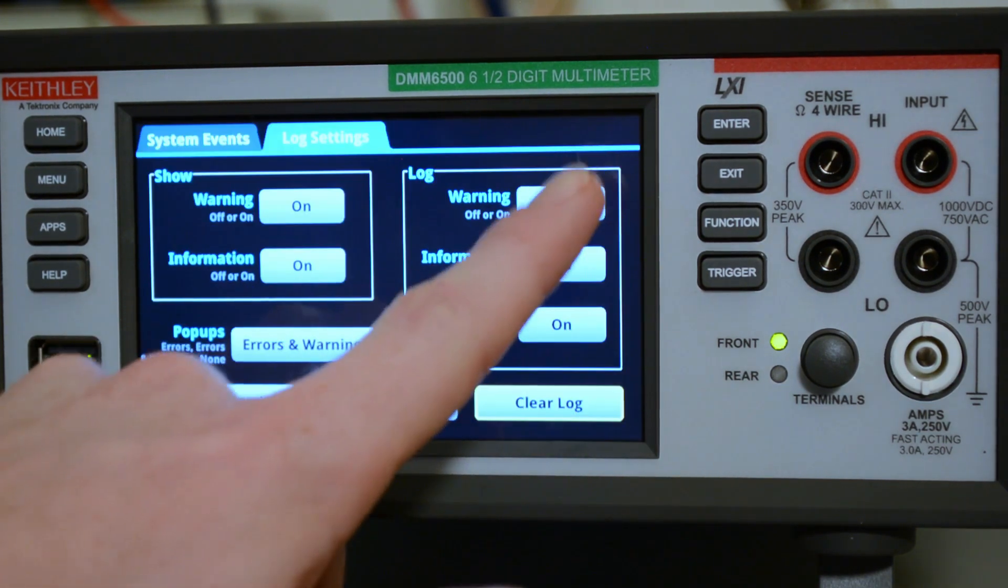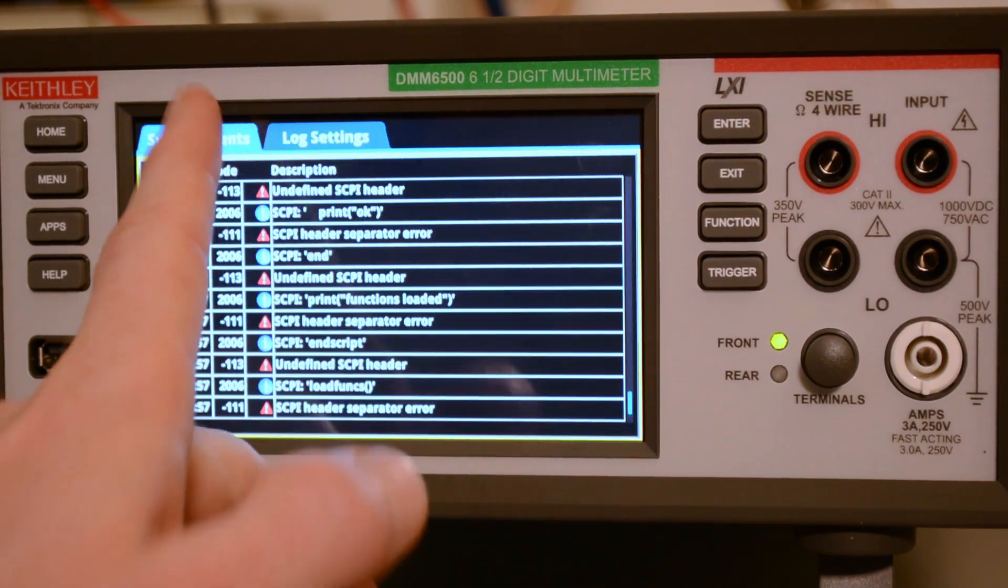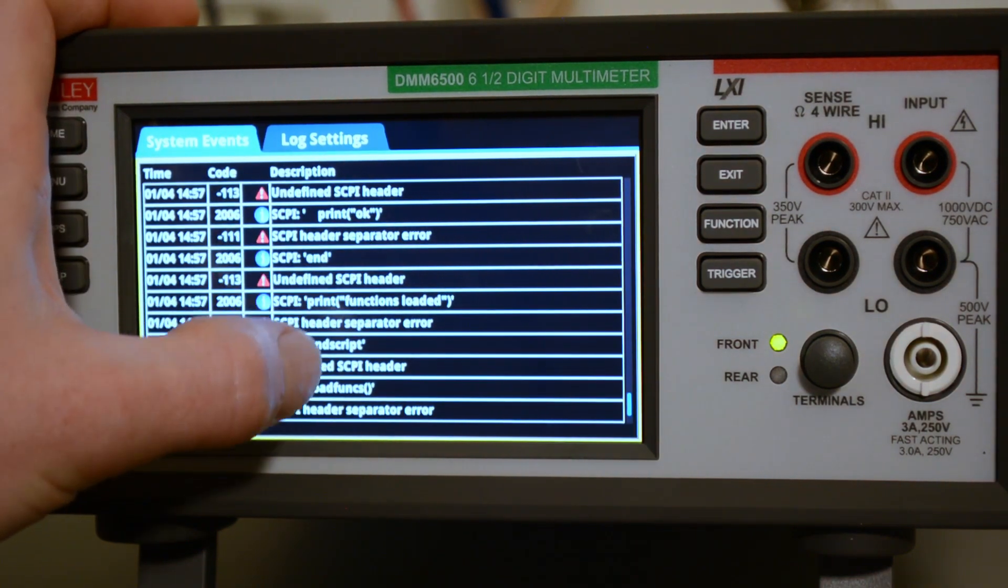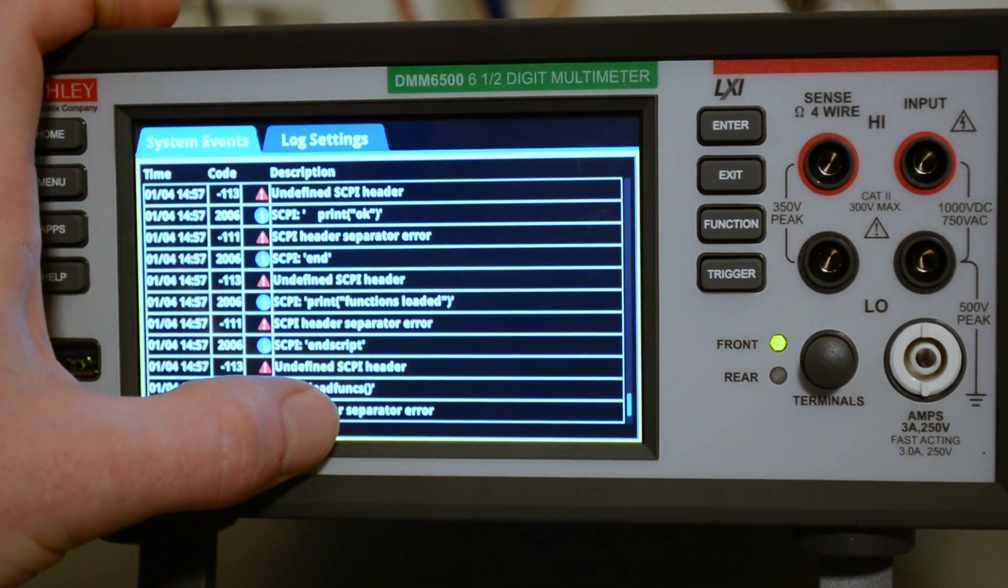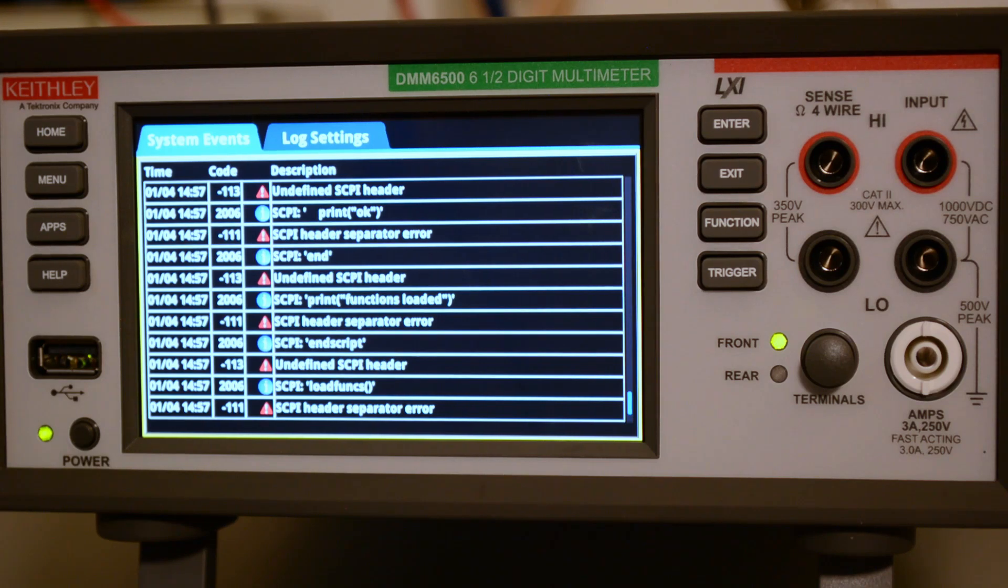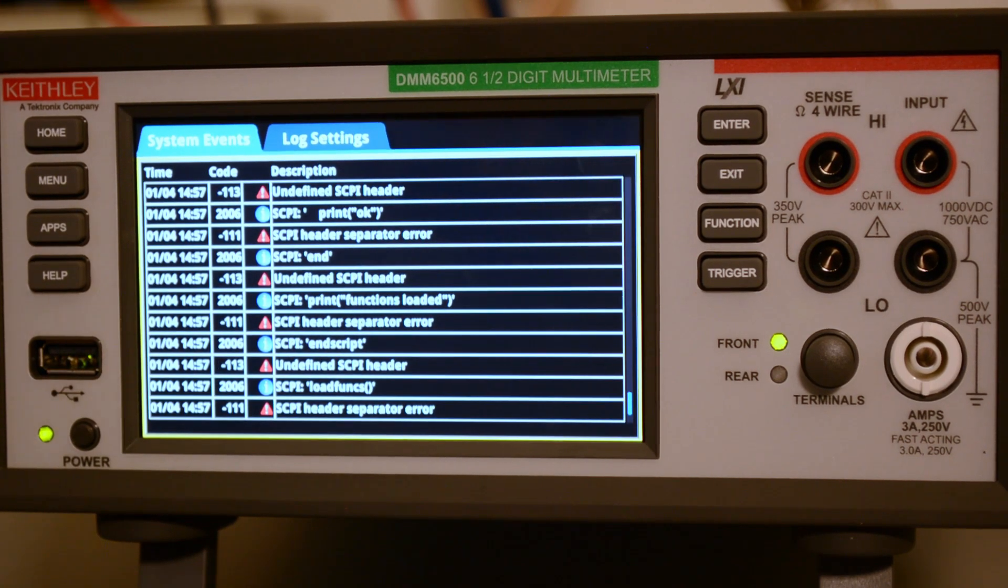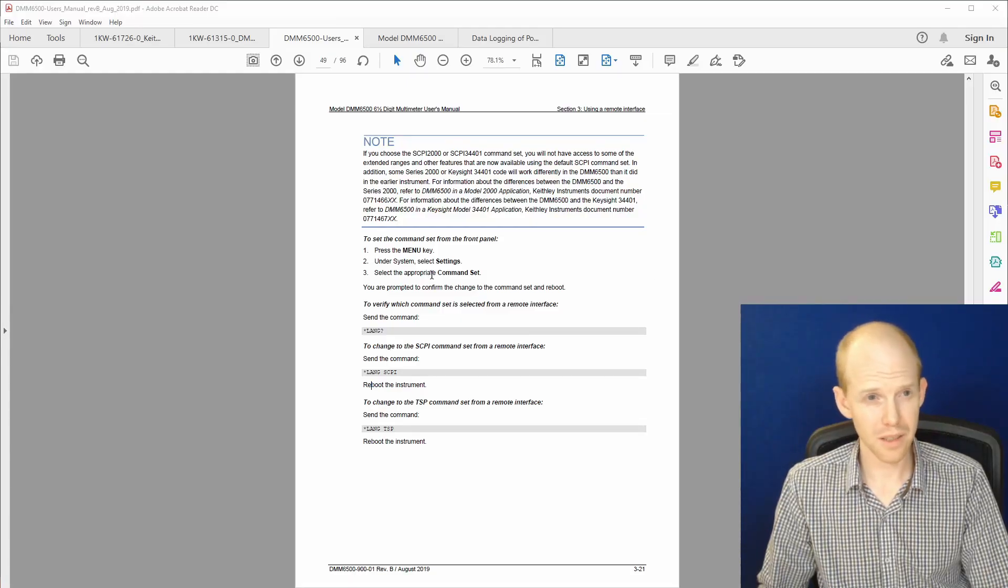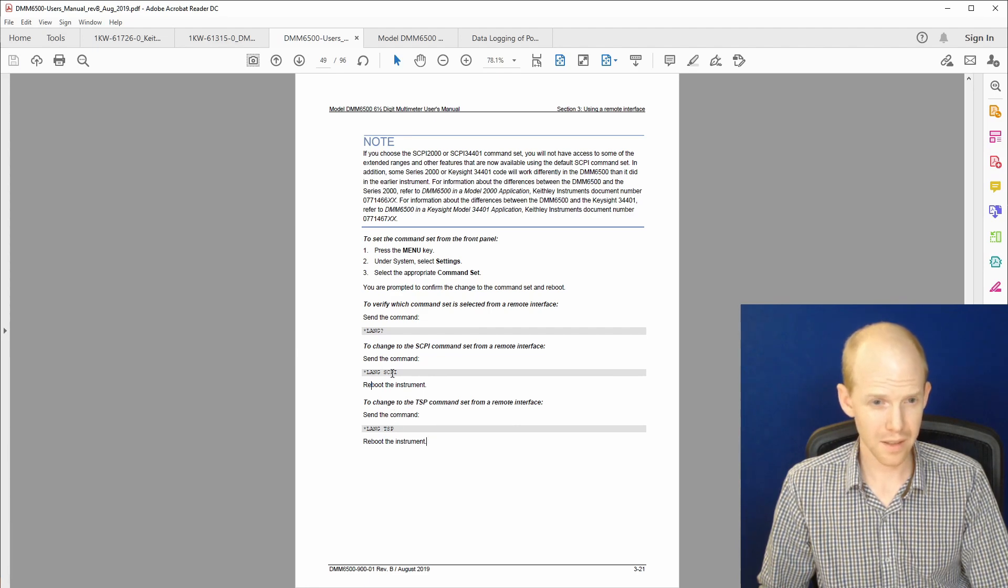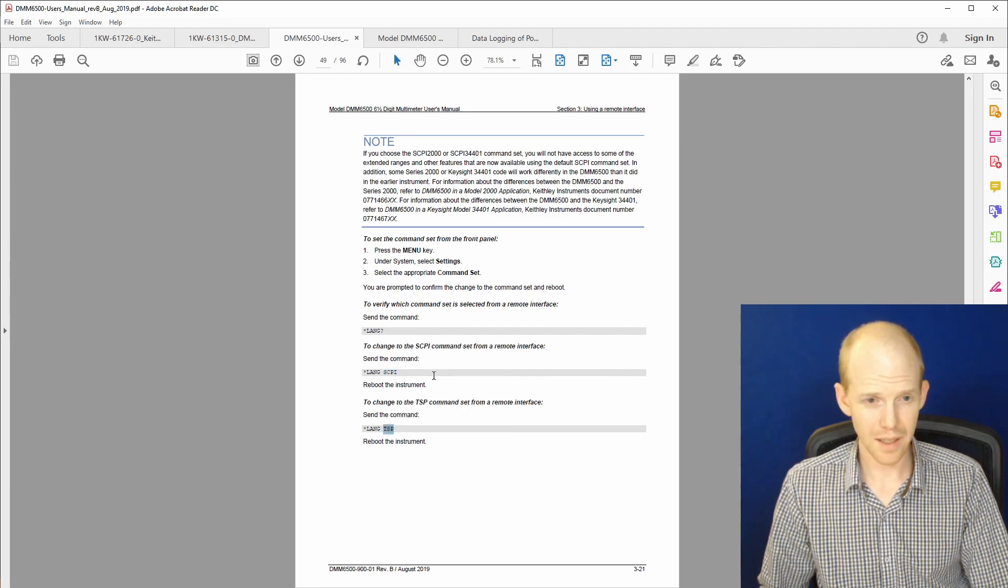And if we go to the error log, here we go. Undefined SCPI header. Print OK. And print function loaded. So it looks like it thinks that this whole script we're loading is SCPI, which it's not. So I think we need to change that. Skimming this user's manual here on page 49, it looks like it's talking about different command sets. And we're using this TSP script. So I think the problem is it's set to SCPI and we need to change it to this TSP command set. So let's try that.